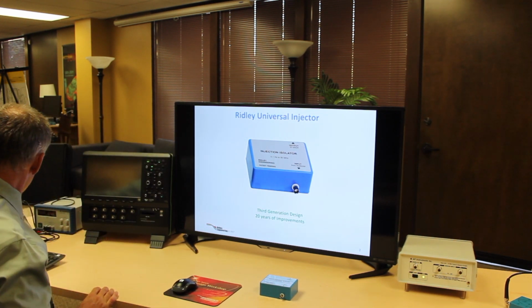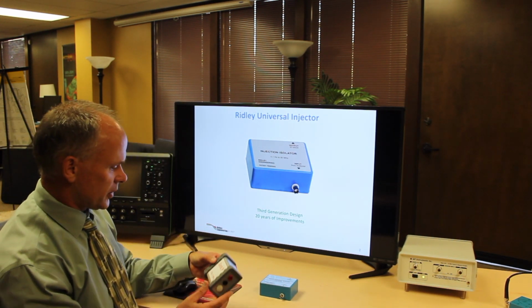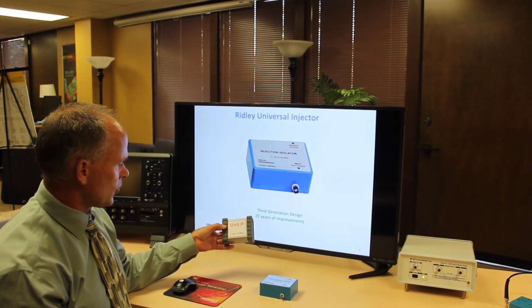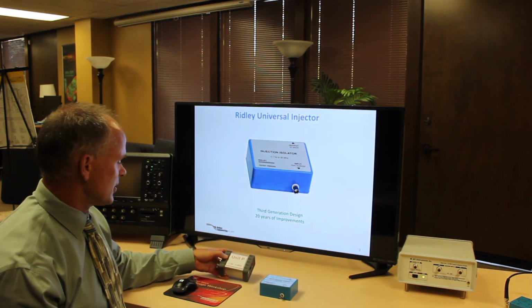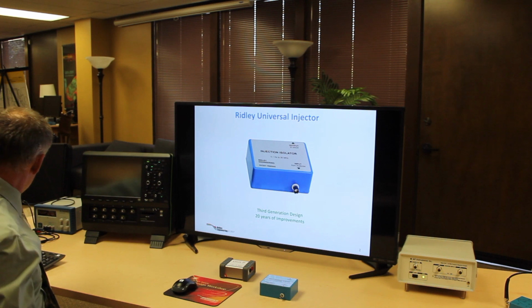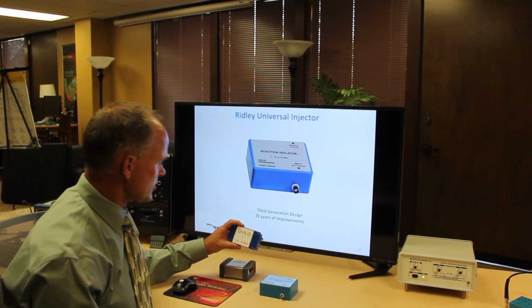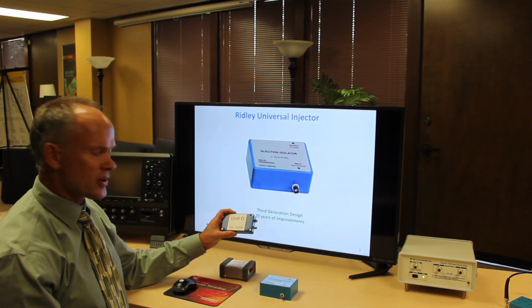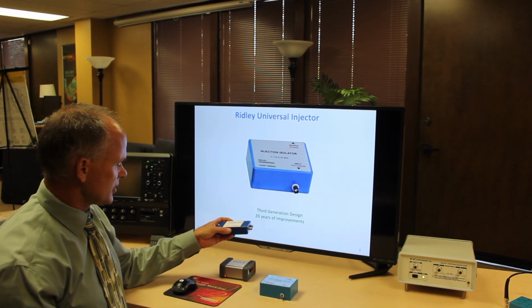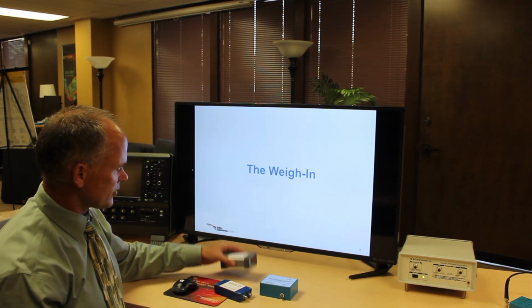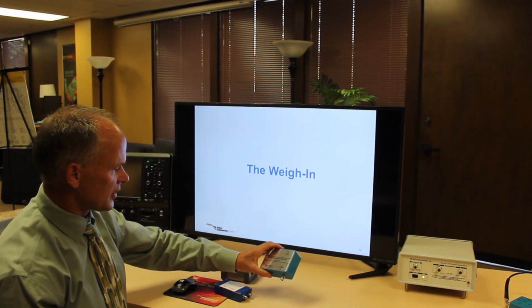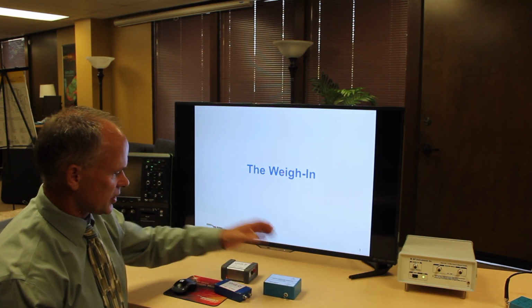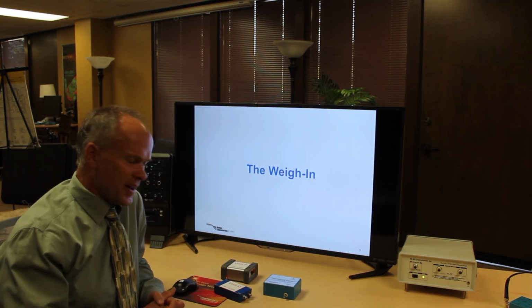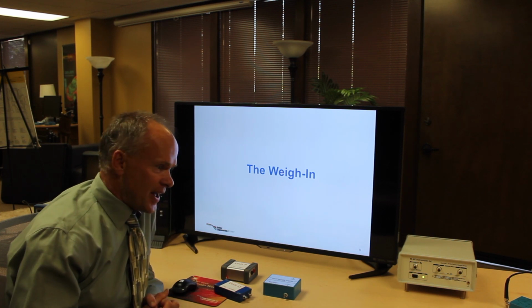There are two other transformers here. One we're going to call Unit P, supposed to go from 1 Hertz to 5 megahertz. Another transformer we have here we'll call Unit O, also supposed to go down to 1 Hertz and up to 10 megahertz. We notice right away both of these transformers are really quite light compared to our injection transformer, which, as a magnetics designer of many decades, always raises a flag with me.